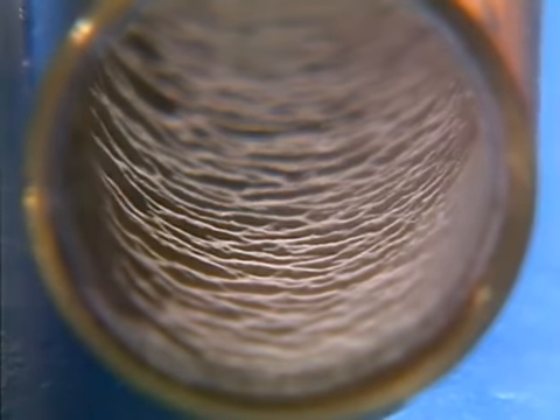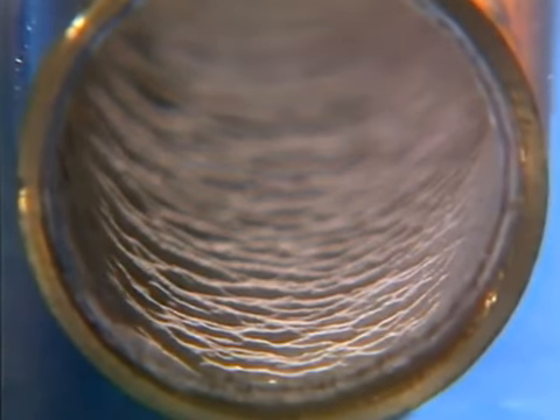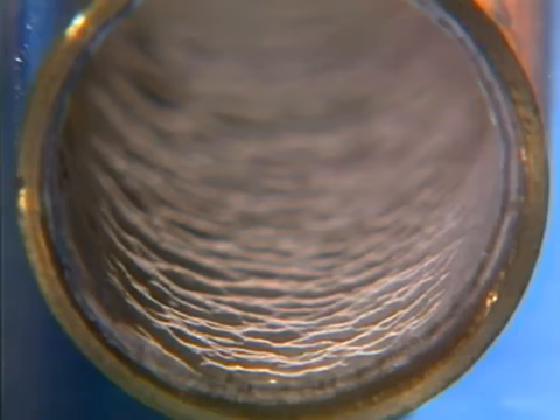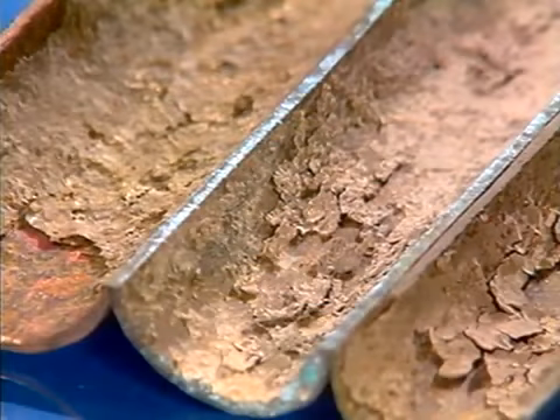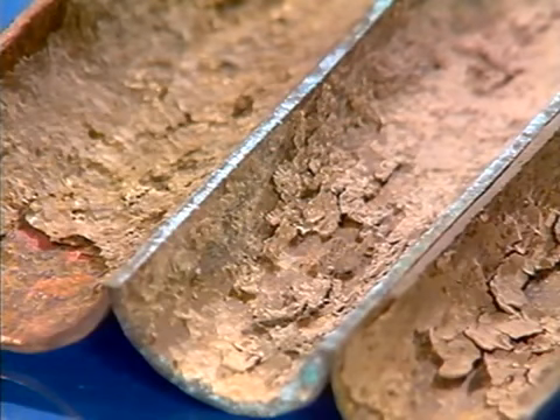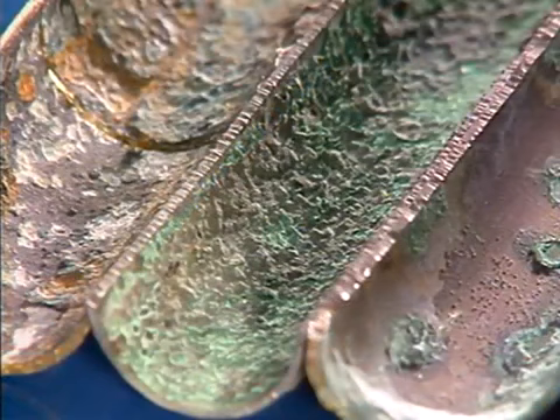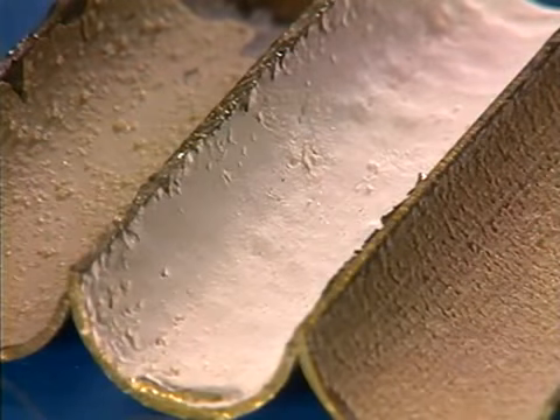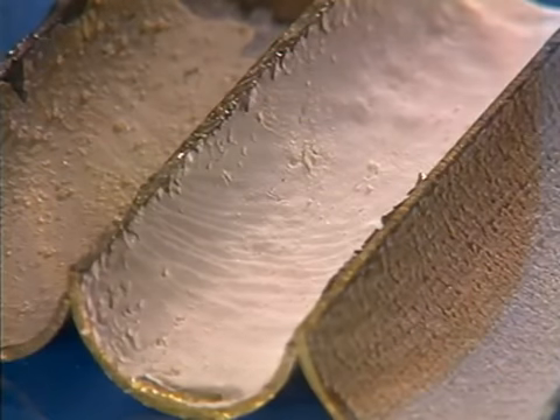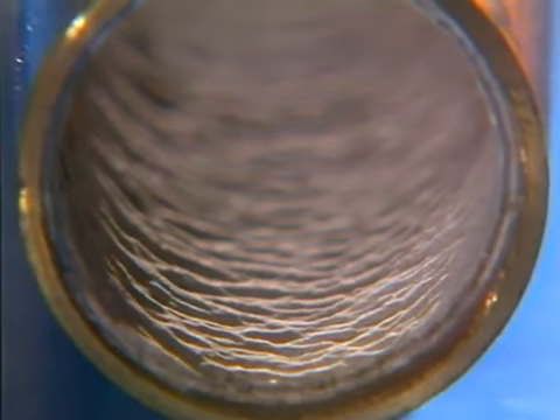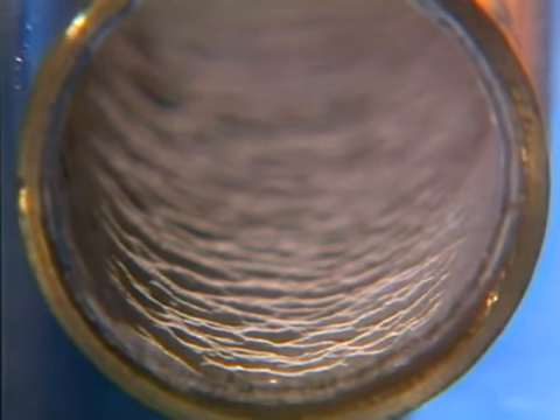In the process, particles in the water contaminate the inner surface of the tubes. River water, for example, typically fouls the tubes with layers of mud. Seawater causes bioslime and sediment, while cooling tower systems attract deposits of calcium carbonate. All these fouling deposits have operating consequences.